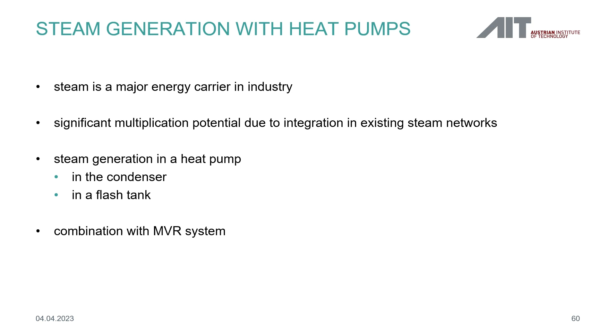It can be done in the condenser, as we have seen before in the presentation of Siemens. This is the thermodynamic optimal solution, because then we have the least number of energy transfer steps. So we use the condenser to condense the refrigerant and evaporate the water that is then used as steam in the process. But steam can also be generated in a flash tank, after producing the high temperature with the heat pump. So this is also interesting for retrofitting existing water-to-water heat pumps into a steam generating unit. And we can combine it with an MVR system. I will show you examples for those activities.